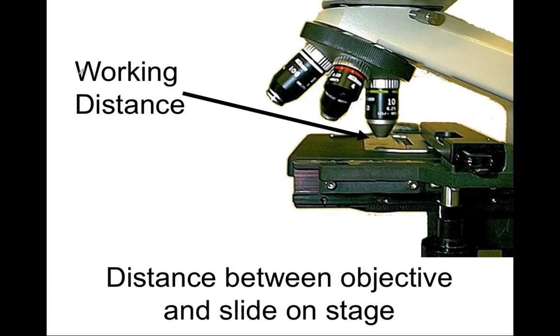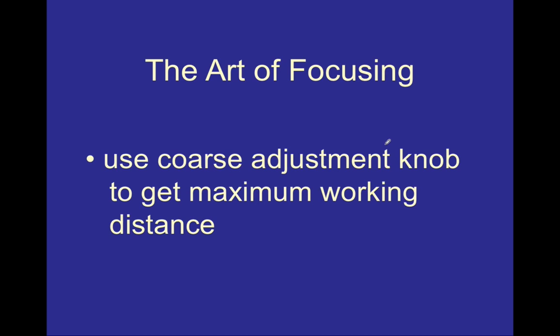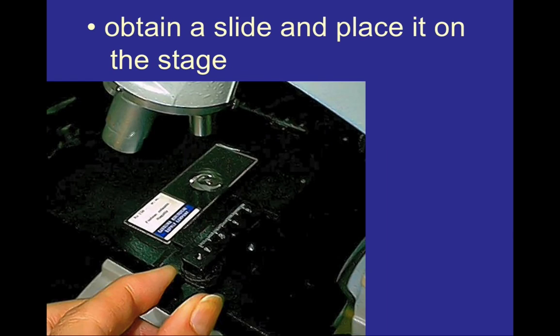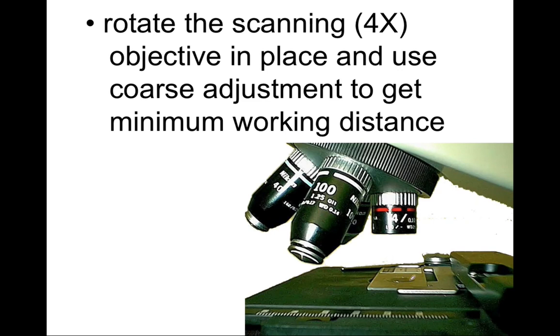The working distance is the actual distance between the edge of the objective lens and the microscope slide sitting on the stage. Working distance is also affected by total magnification. As you are taking a new microscope slide and getting ready to view it, you always want to make sure the working distance is at its maximum. The coarse adjustment knob adjusts the working distance between the objective lens and the stage, so increase that working distance as much as possible before placing a microscope slide onto the stage to ensure you're not damaging the objective lenses.